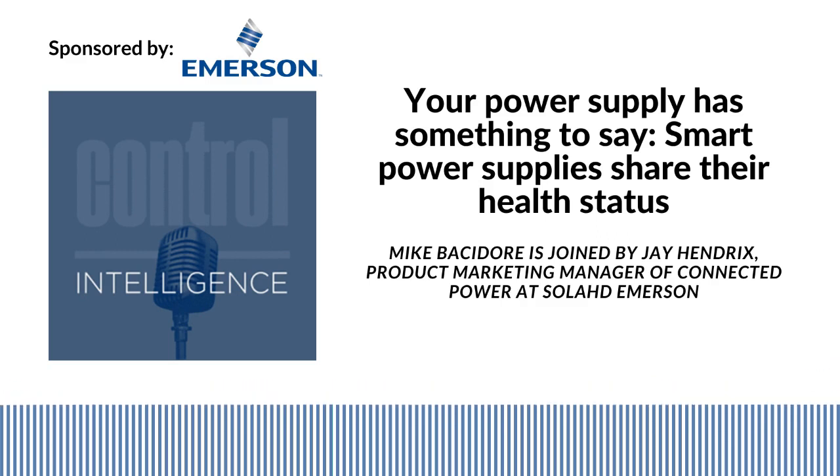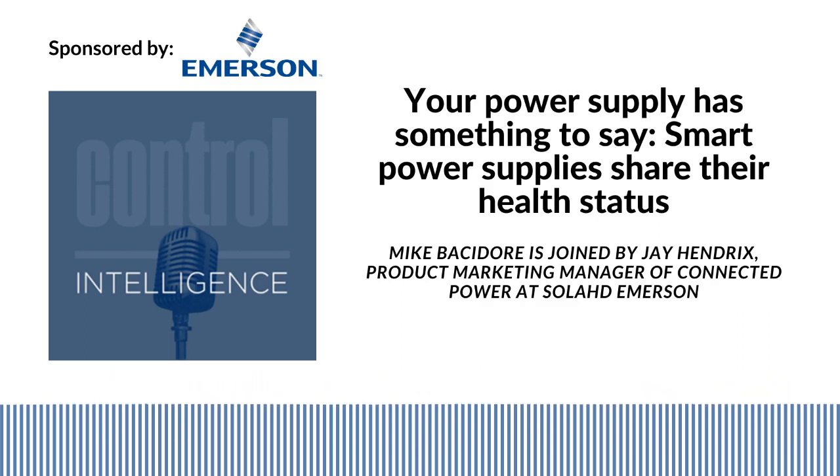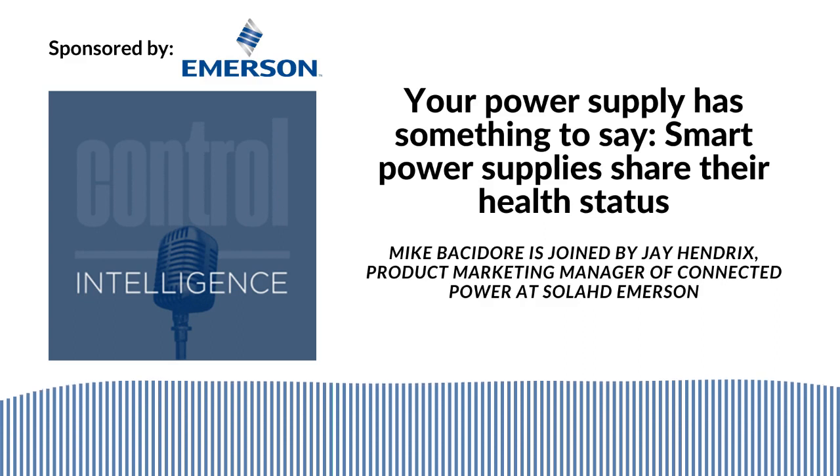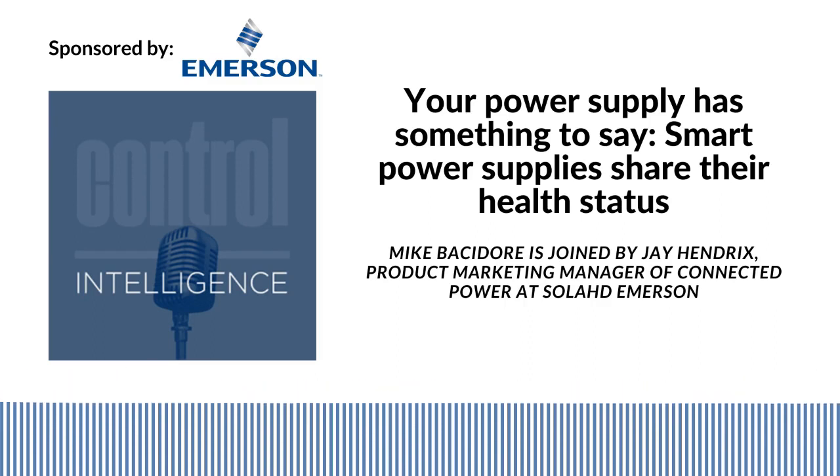What specifically are the benefits to monitoring 24-volt DC power supplies? Well, we get asked that question a lot, actually, Mike. People tend to buy their power supplies and put them in a cabinet, and they seem to last forever, and that's a good thing. But connectivity actually provides you a window into your power supply's health. And that gives you the ability to monitor where you couldn't in the past. Through this connection, diagnostic information is communicated on the network to the control system. This allows the operators to monitor and trend key information from the power supply, alerting them when critical events are occurring. And this enables you to catch the problems, hopefully before they occur, because once things go haywire, it's too late at that point.